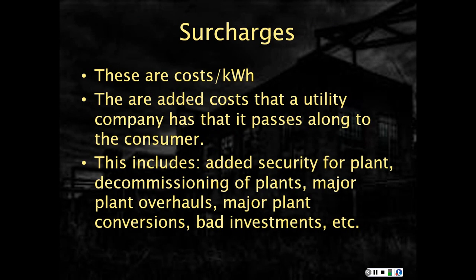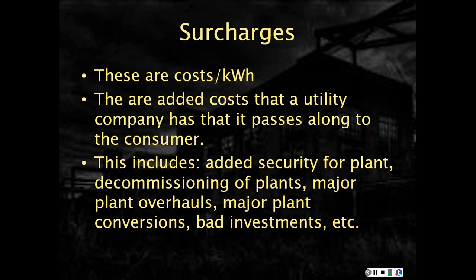The fourth element in a consumption-based bill is surcharges. These are also costs per KWH — added costs that a utility company has to pass along to consumers. This may include everything from added security for the plant, decommissioning of certain types of plants like nuclear plants, major plant overhauls, major plant conversions, bad investments, and storm coverage such as damage after a hurricane or an ice storm. These are all added costs allowed by governing bodies for utility companies to charge above and beyond the normal generation, transmission, and distribution of electricity.